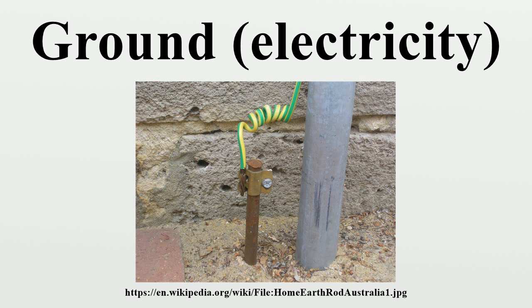The US NEC and the UK's BS 7671 list systems that are required to be grounded. The grounding electrode conductor connects the leg of the electrical system, that is the neutral wire, to the grounding electrode. The grounding electrode conductor is also usually bonded to pipework and structural steel in larger structures. According to the NEC, the purpose of earthing an electrical system is to limit the voltage to earth imposed by lightning events and contact with higher voltage lines, and also to stabilize the voltage to earth during normal operation.